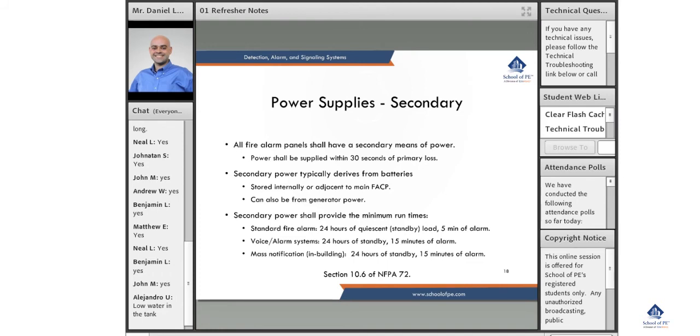These are typically done by engineers, but usually by a licensed fire alarm technician during the submittal phase. They're verified to have a certain amount of power available, to have a certain safety factor built in, and then the batteries are sized and placed. You can also power it from the generator.